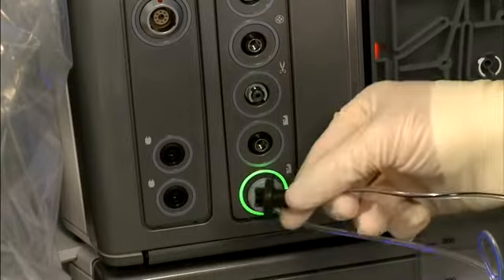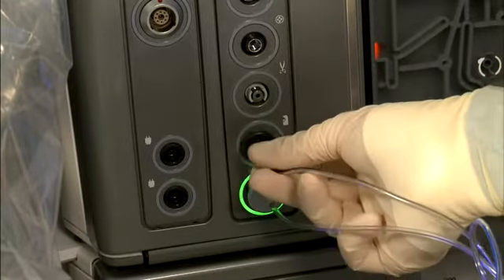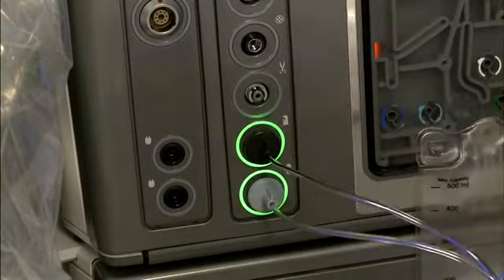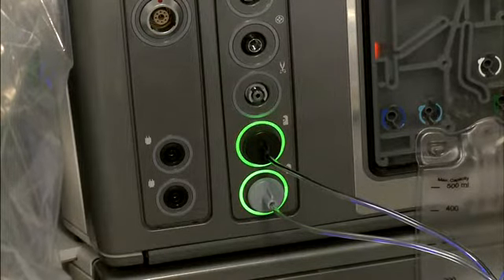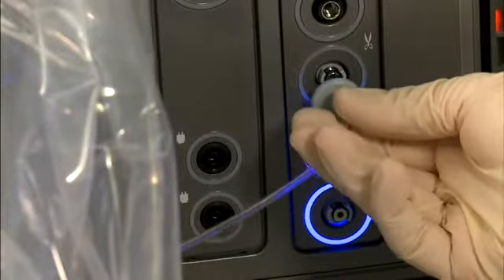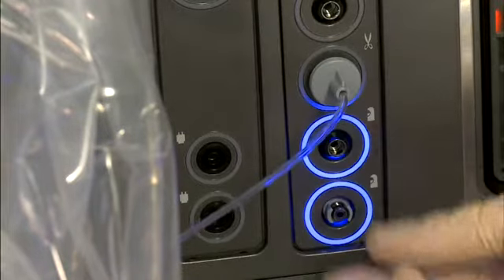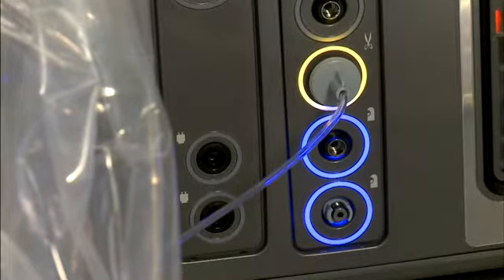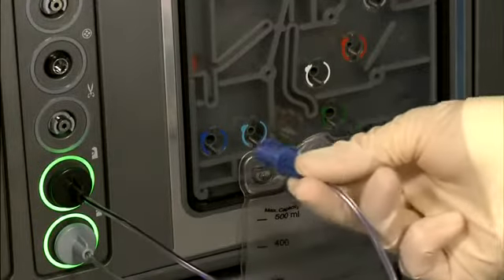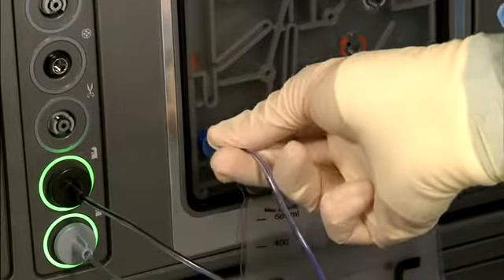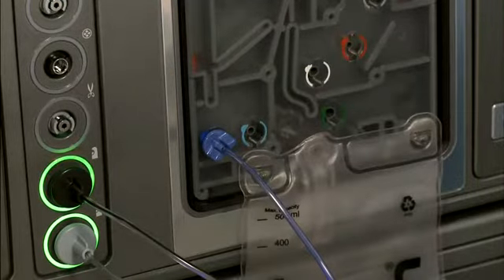The flange on the connector acts as a sterile barrier, so this task can be performed by the sterile scrub nurse. The radio frequency identification rings will illuminate green when attached. If the connector illuminates amber, this indicates that the handpiece has been connected to the wrong port. Connect the dark blue vitrectomy probe vacuum line to the cassette and turn clockwise until fully engaged, or about 2 clock hours. The connector and cassette ports are color-coded and keyed for ease of identification.